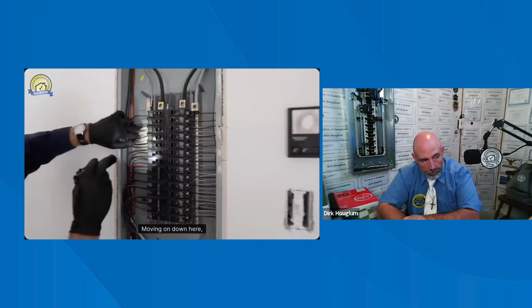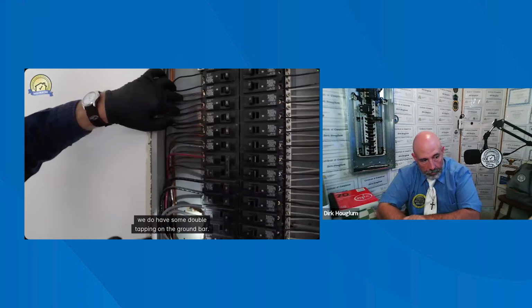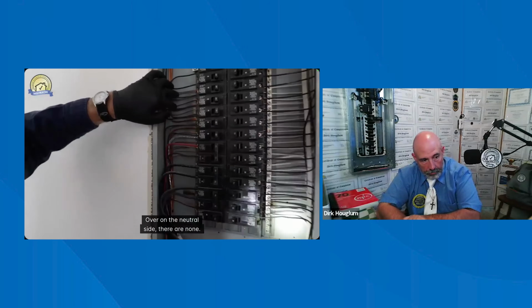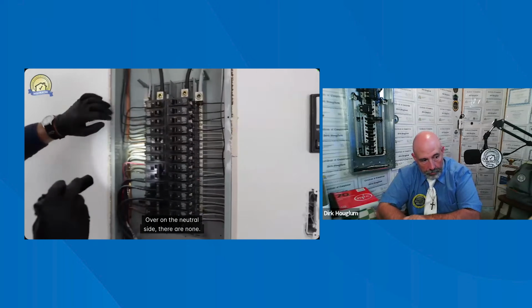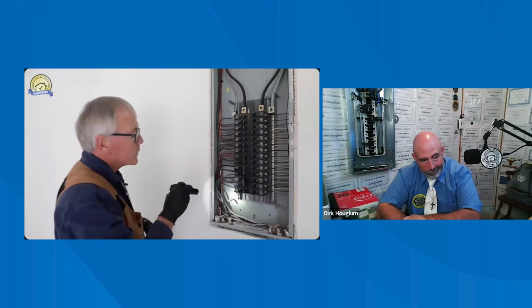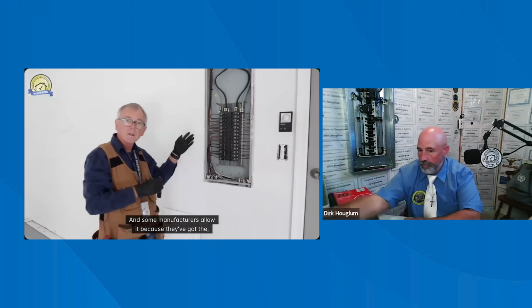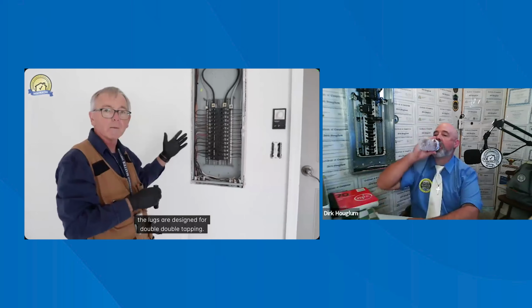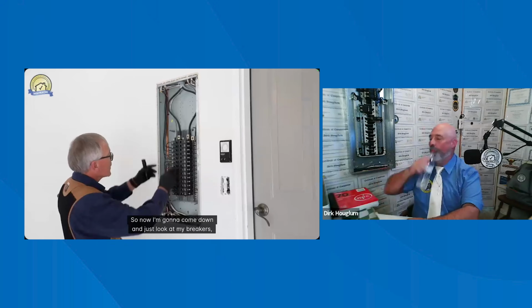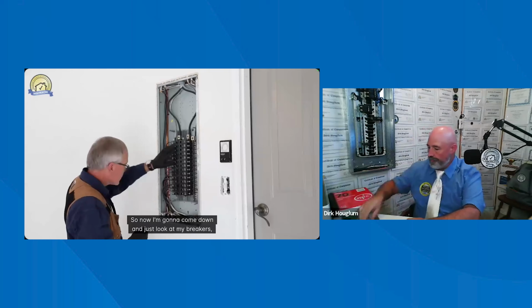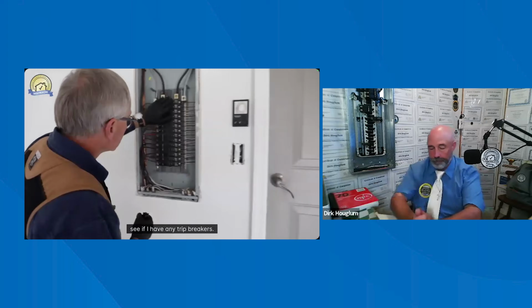Okay, moving on down here, we do have some double tapping on the ground bar. Over on the neutral side, there are none. Now typically, double tapping was allowed in certain years, so you can note this. And some manufacturers allow it because the lugs are designed for double tapping. So now I'm going to come down and just look at my breakers, to see if I have any tripped breakers.